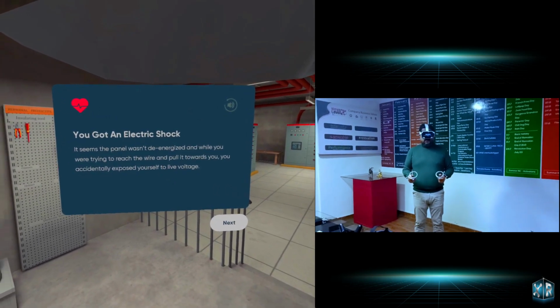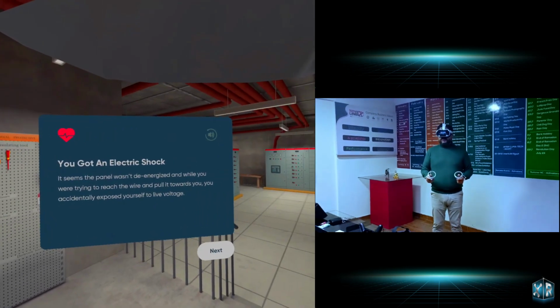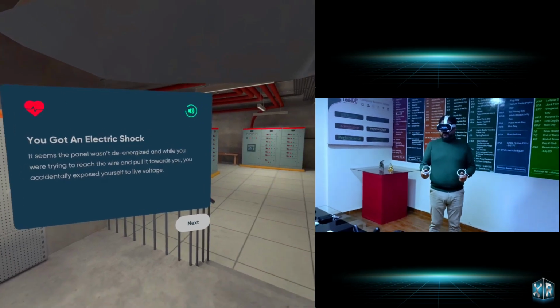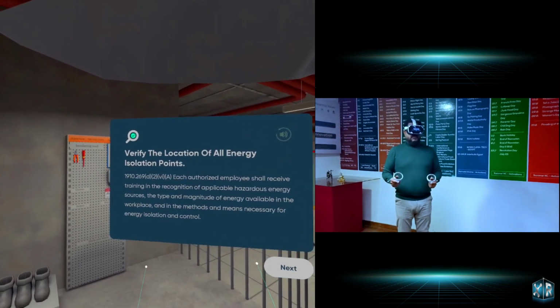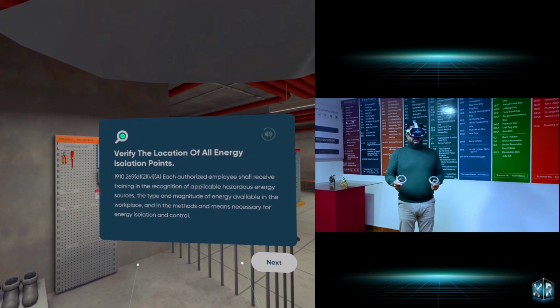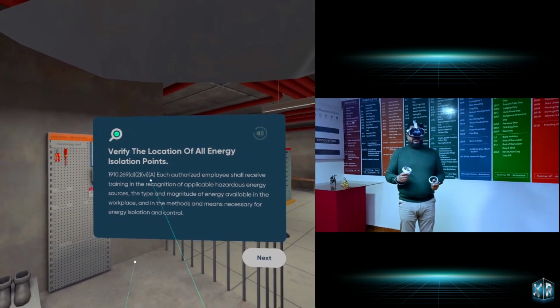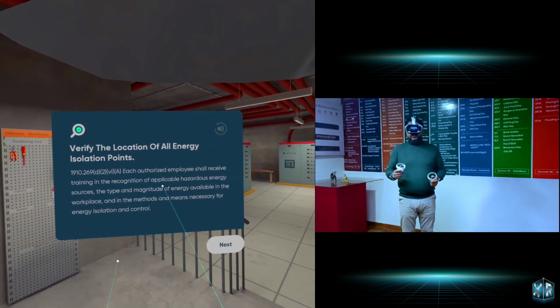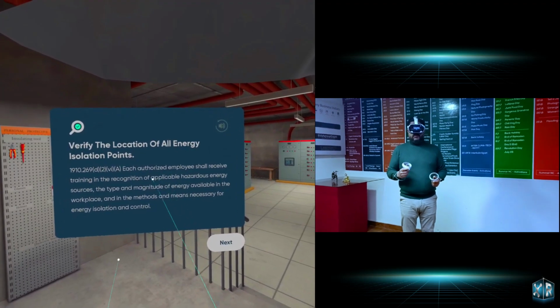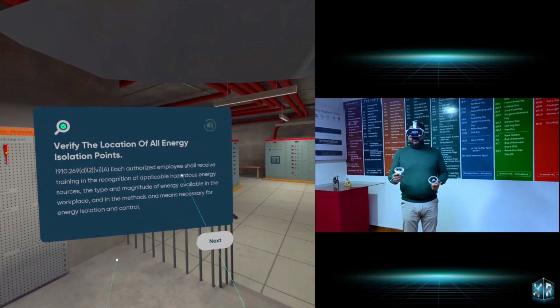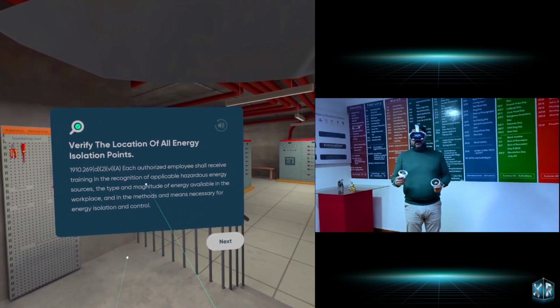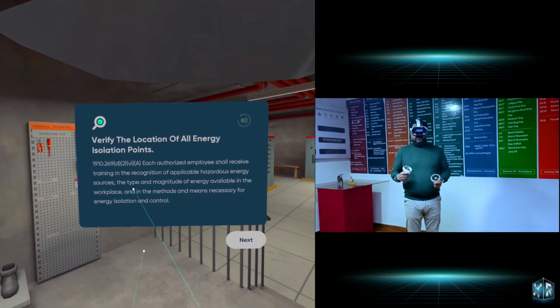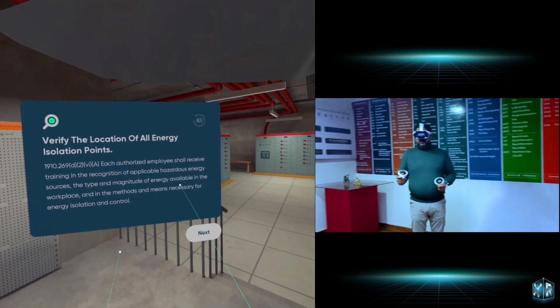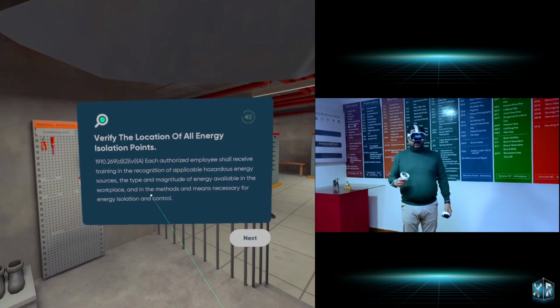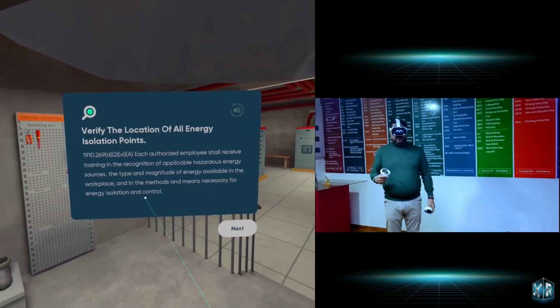Let's have a look at some of the contributing factors that led to this fatality. Verify the location of all energy isolation points. An employee should verify the location of all energy isolation points. According to the OSHA standards, each authorized employee shall receive training in the recognition of applicable hazardous energy sources, the type and magnitude of the energy available in the workplace, and the methods and means necessary for energy isolation and control.